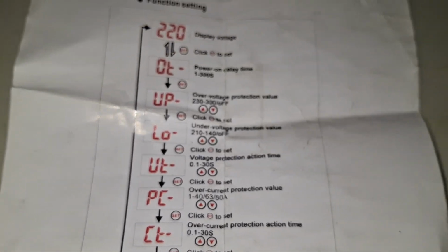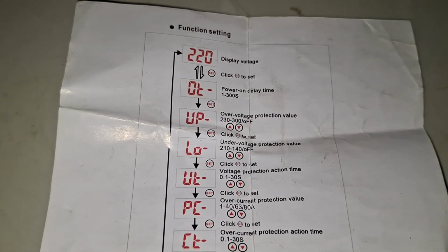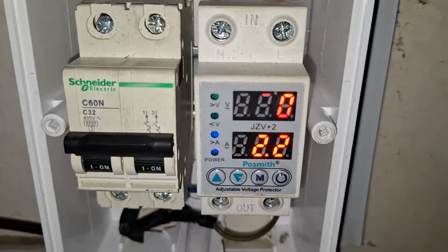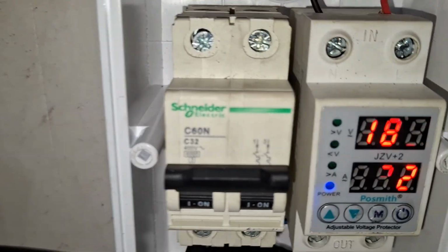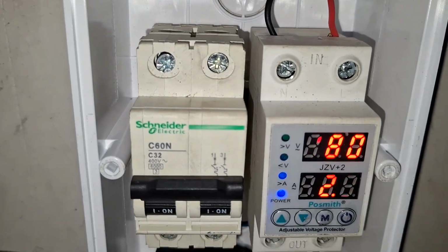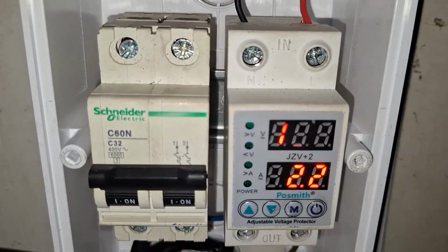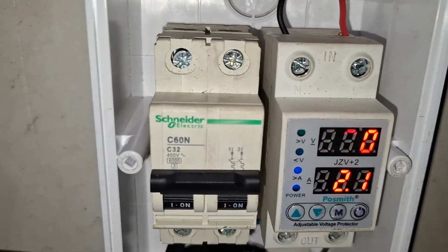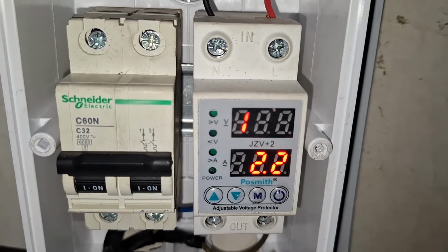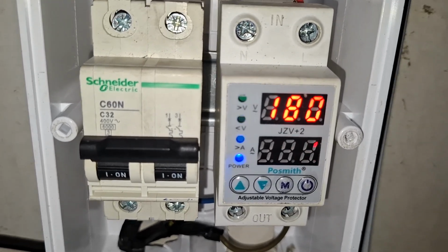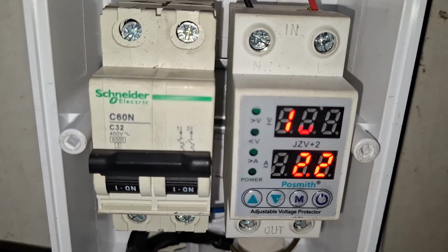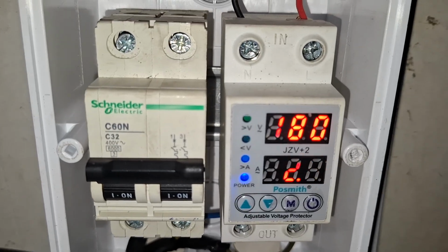But I want to say something here. AVP is used to connect between AC input and AC output. When you are connecting AC input to your inverter, you are protecting the inverter from your grid power surge, either voltage or current. But when we use AVP for AC input, we prioritize voltage. So we use AVP for AC output to prioritize current. That is why we have to set the amount of current that our inverter will take.